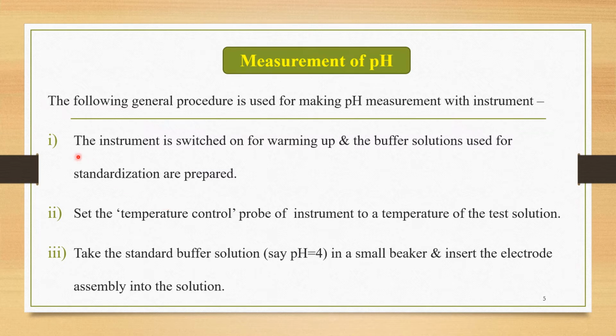The first important step is that the instrument is switched on for warming up, and the buffer solutions used for standardization are prepared. So first of all, we have to switch on the instrument for warming, and meanwhile we have to prepare some buffer solutions for the standardization of this pH meter. The second step is to set the temperature control probe of the instrument to the temperature of the test solution. So we have to adjust the temperature to a particular value with the help of the temperature control probe. The third important step is to take the standard buffer solution, say pH equal to 4, in a small beaker and insert the electrode assembly into the solution.